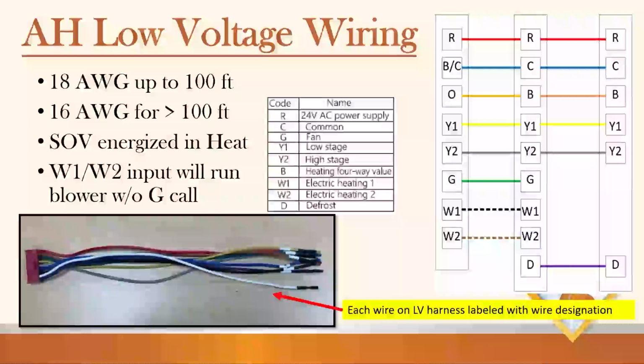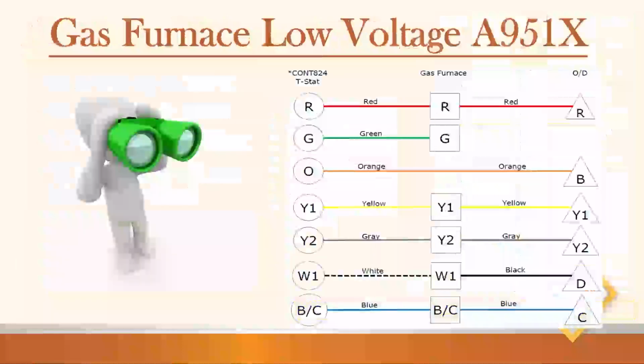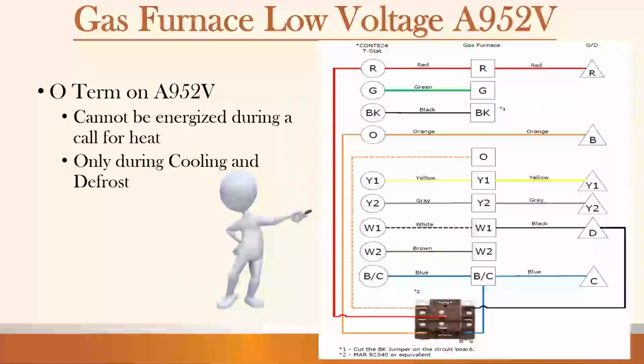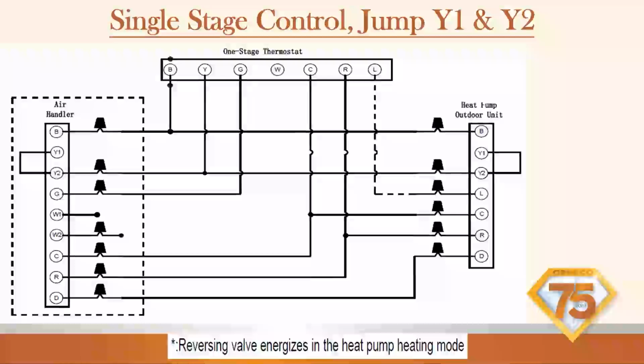There you go, the wiring. Each wire on the low voltage harness is labeled with its wire destination, so they make that pretty easy. Again, the reversing valve is energized in heat. Anything over 100 foot of thermostat wire needs to be 16 gauge. There's our low voltage on an A951X. On the A952 variable speed, we have to add that relay for the reversing valve to energize orange. Single stage, we want to just jump Y1 to Y2.